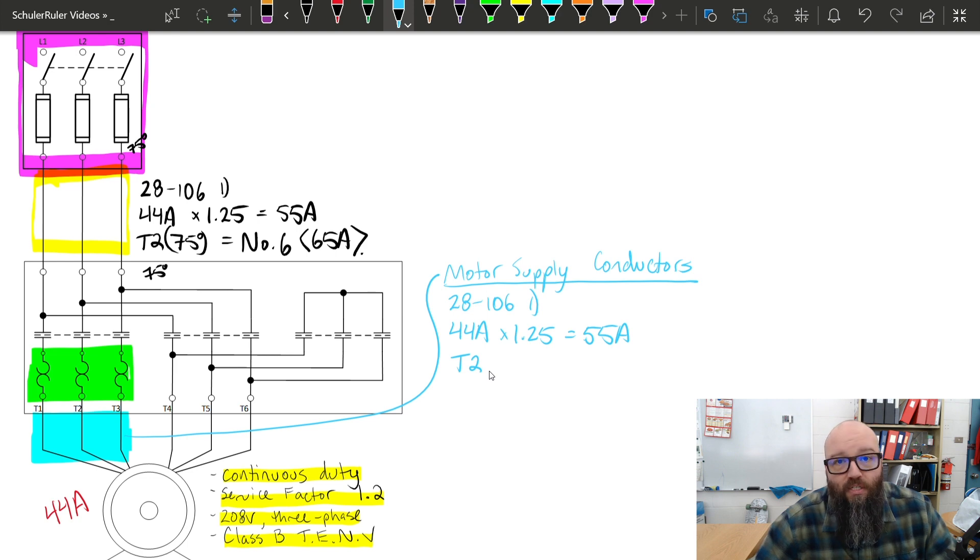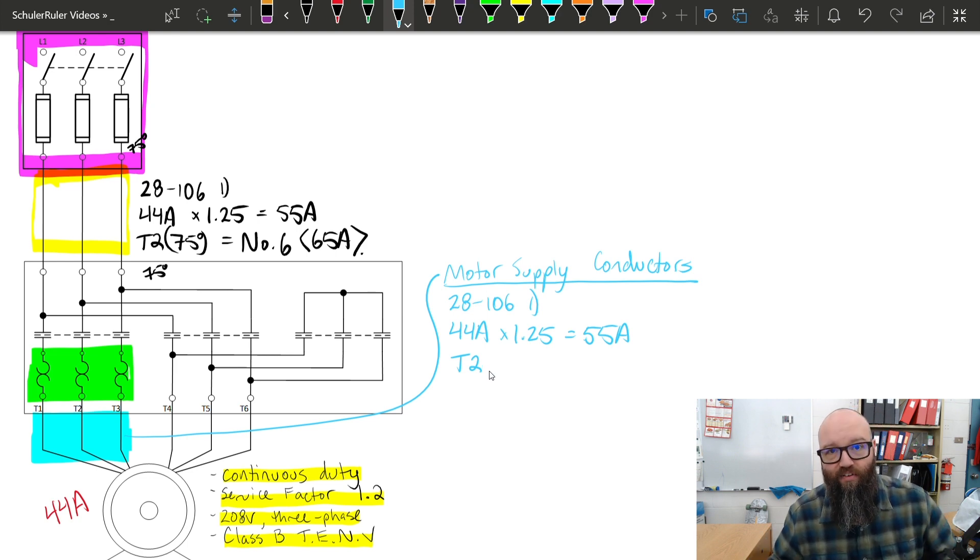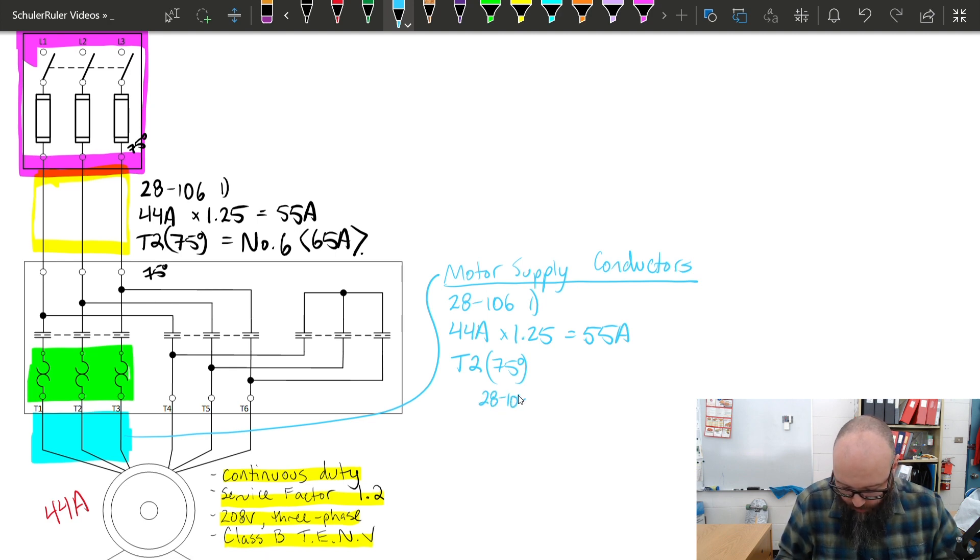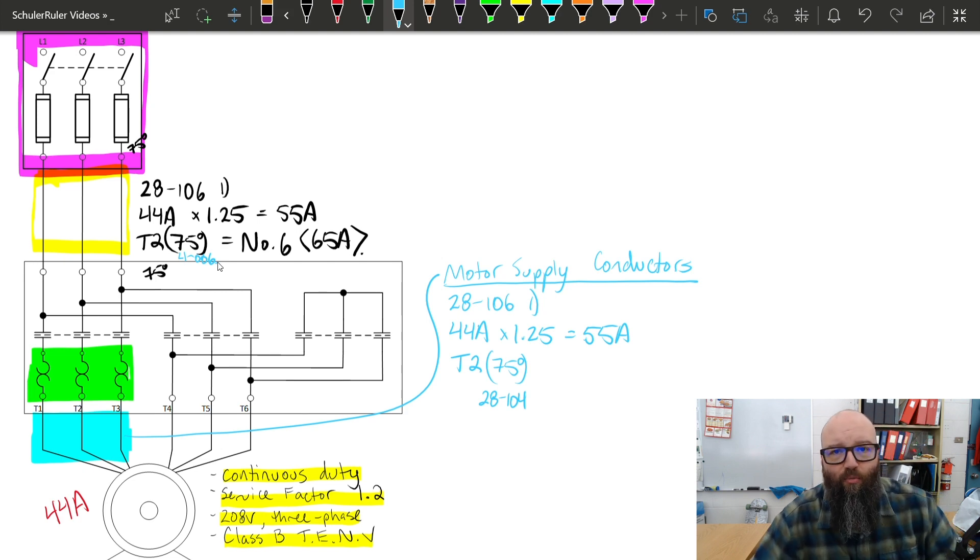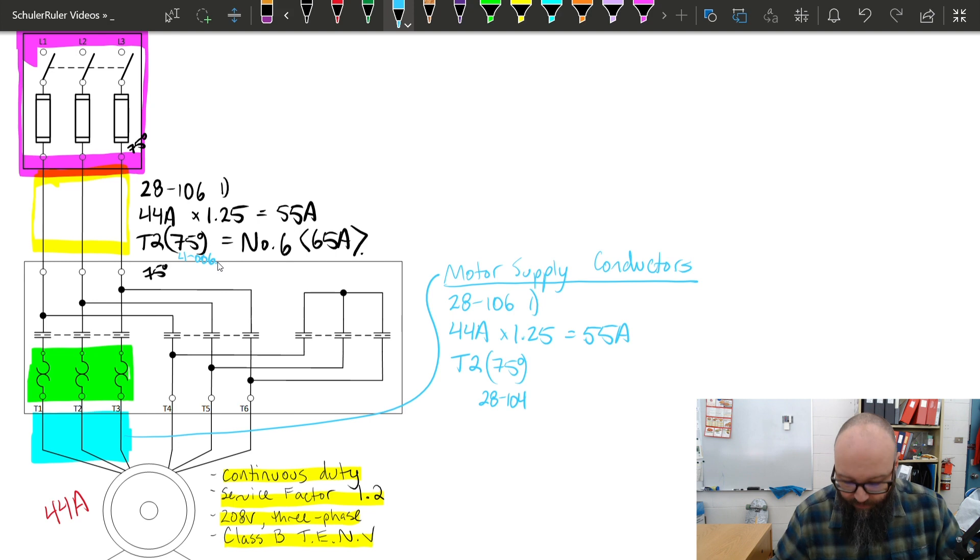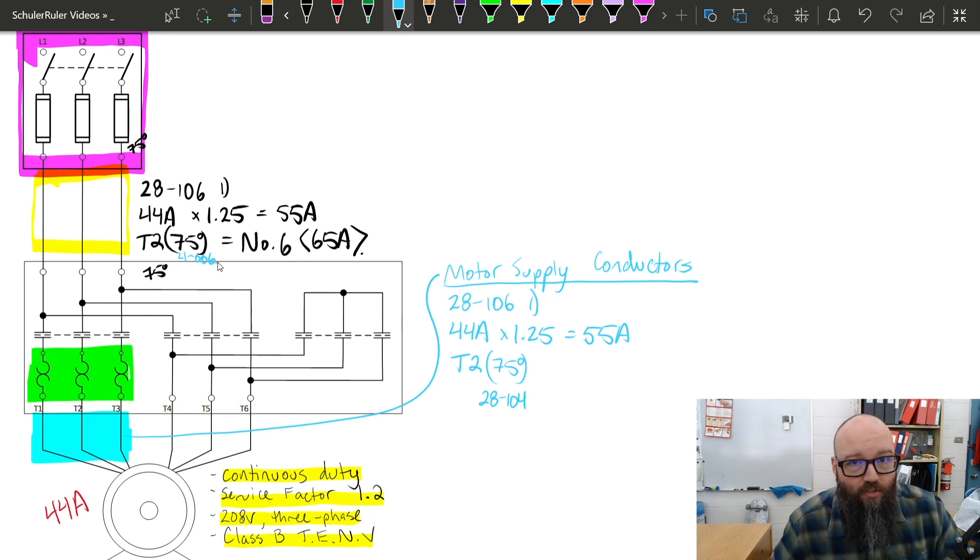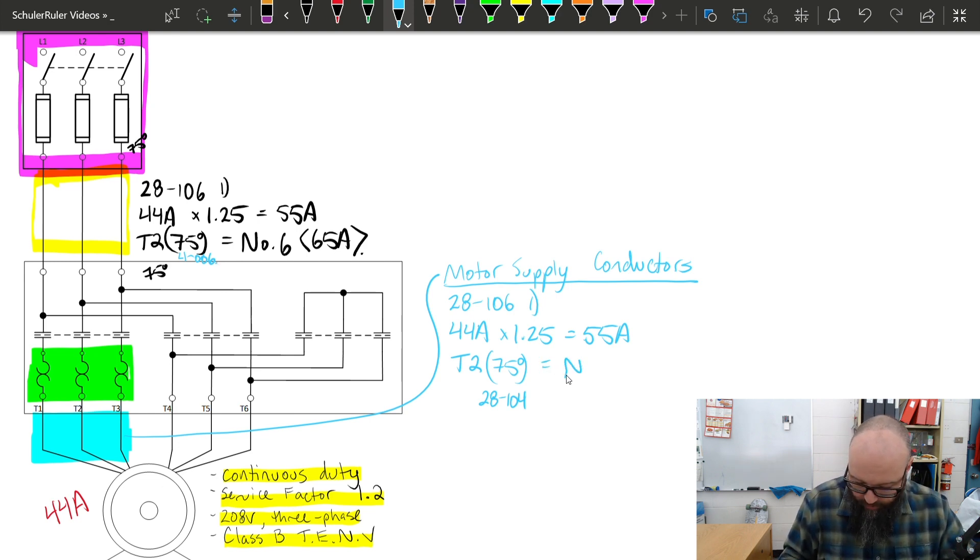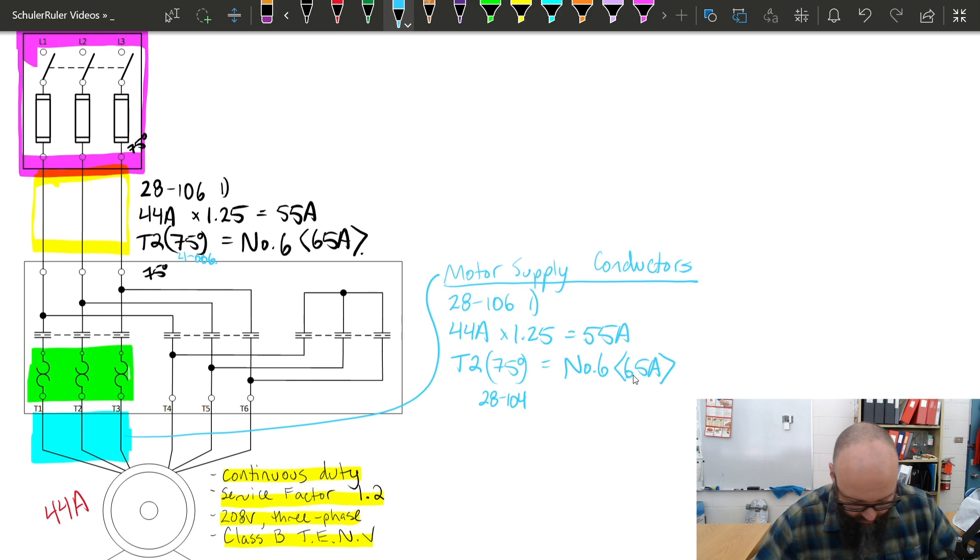Table 2, 75 degrees. This is 28-104 that requires that I use the 75 degrees here, whereas my number 6 up here, this was 4006, lowest termination temperature that required I use 75 degrees there. So just a little bit of kind of clarification on that motor supply versus branch circuit. It's not specific to a Y delta start. It's just good to always revisit that fact. So, we end up with the same size conductor, essentially. We're looking at a number 6 with a 65 amp rated ampacity, again, from table 2.